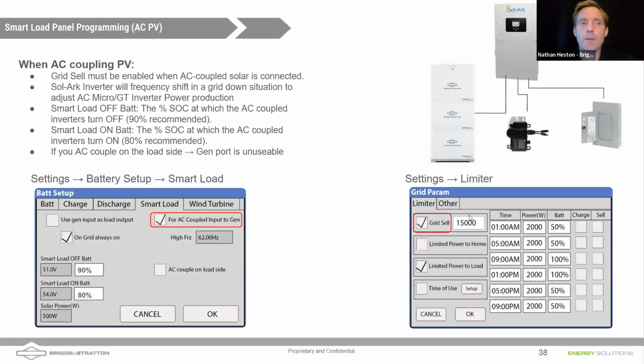What about for AC coupling? How would we program a Sol-Ark to let it know that we've got AC coupled PV coming in through the generator port and not a generator? Daniel, what are the things that we should be doing for AC coupled PV in the smart load settings? Well, we want to make sure we check for AC coupled input to the generator. Make sure that we have grid sell enabled, and then we're going to set some of those smart load off and on tabs right here.